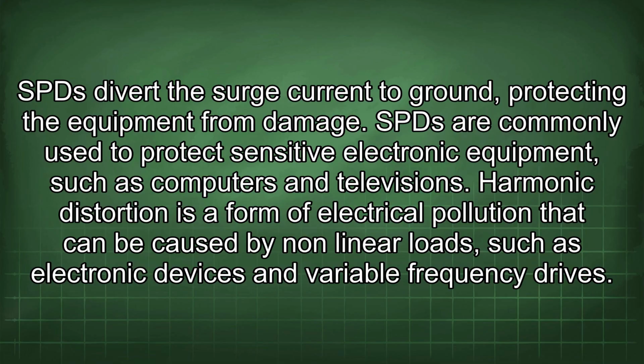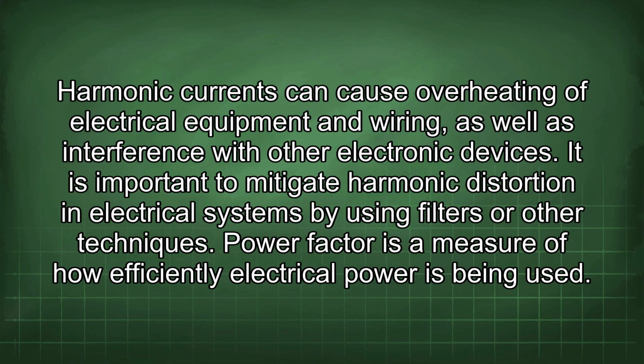Harmonic distortion is a form of electrical pollution that can be caused by nonlinear loads such as electronic devices and variable frequency drives. Harmonic currents can cause overheating of electrical equipment and wiring, as well as interference with other electronic devices. It is important to mitigate harmonic distortion in electrical systems by using filters or other techniques.